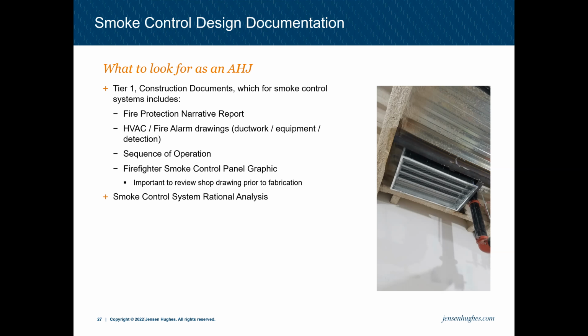If it's a very complex system, such as an atrium, we definitely recommend having that smoke control panel in there to make sure it's coordinated and bid correctly. Also, in the design documents, the smoke control rational analysis should be included for the AHJ's review and approval with the project.